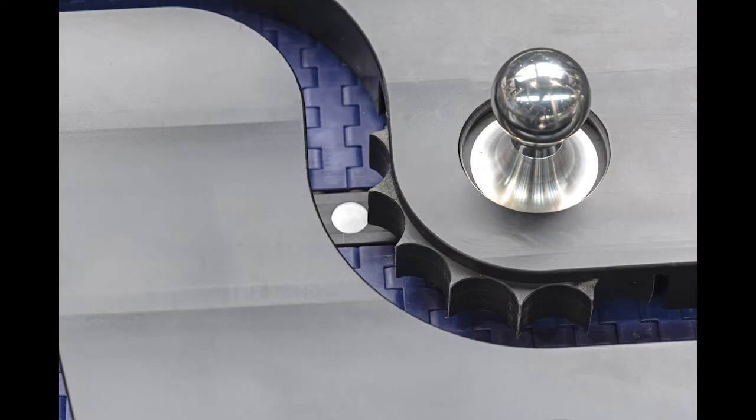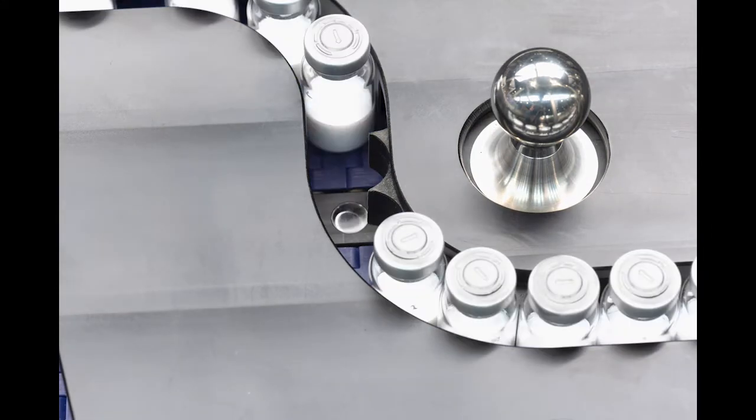Using the Lyo-Essence system from GEA, our clients are able to detect the residual moisture of the freeze-dried product in real time. The measurement happens directly during the unloading process before the vials have been passed downstream for further processing. With this technique, Lyo-Essence can measure 100% of the vials coming out of a freeze dryer.